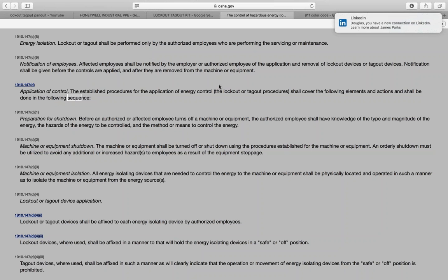And then also dissipate any stored energy by attaching the equipment to a system, to a ground, or opening up any valves. Verifying that the test equipment is functional using a known power source. Also confirming that all switches are in the open position and that we use test equipment to verify.